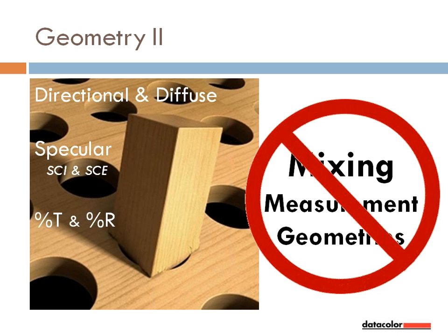And the terms specular included, abbreviated SCI, and specular excluded, SCE, add precision and differentiate options on sphere D8 and multi-angle design. Remember, don't expect measurements made with one geometry to agree with those made using another.